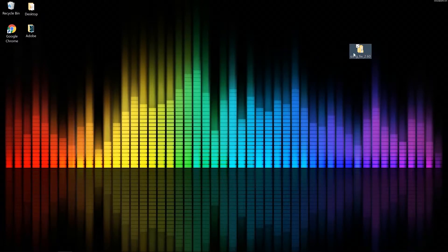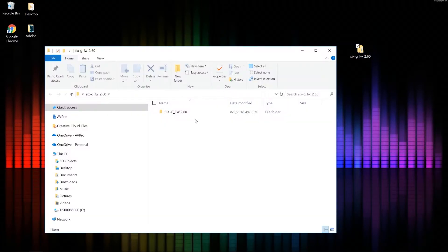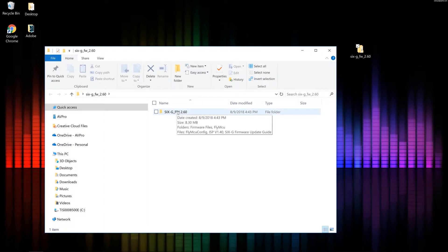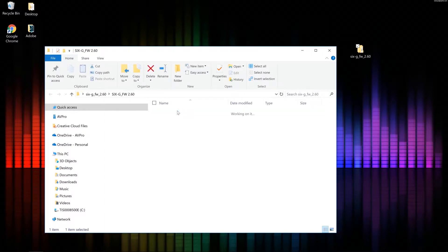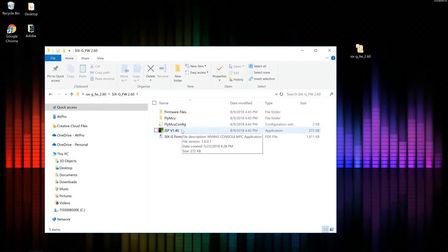Okay, so I'm going to go ahead and open it up. We're going to open up the 6G firmware 2.60 folder. Now the firmware is in two steps. Step number one, I need this ISP v1.40 software, so I'm going to go ahead and open that up.